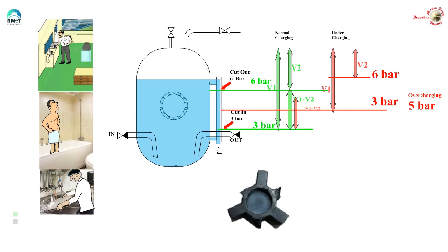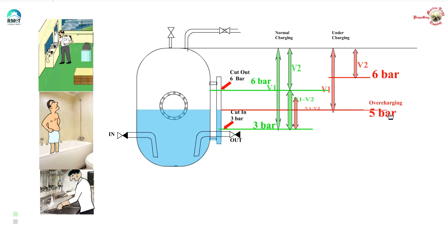Now let us move on quickly. What happens if you overcharge the hydrophore? So somebody has kept the level here and he is now going to charge it to 5 bar. Obviously it is a classic example of overcharging. The pressure here is 5 bar. So now you know that as the water gets consumed, the water level is going to fall. But the cut-in pressure of 3 bar has not yet reached. The water level has gone below the gauge glass. And maybe still the cut-in pressure is not reached. It might also happen that the water level will fall below the outlet pipe.